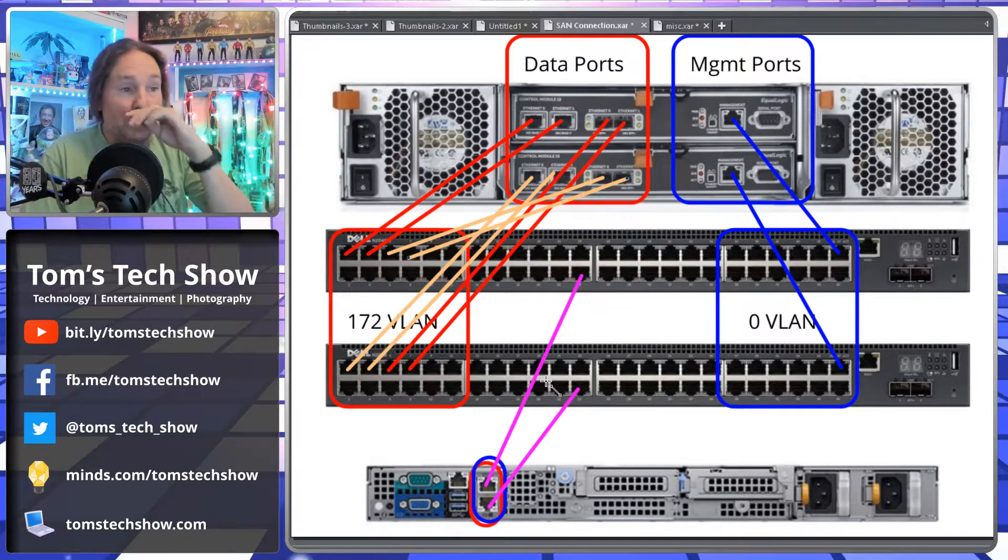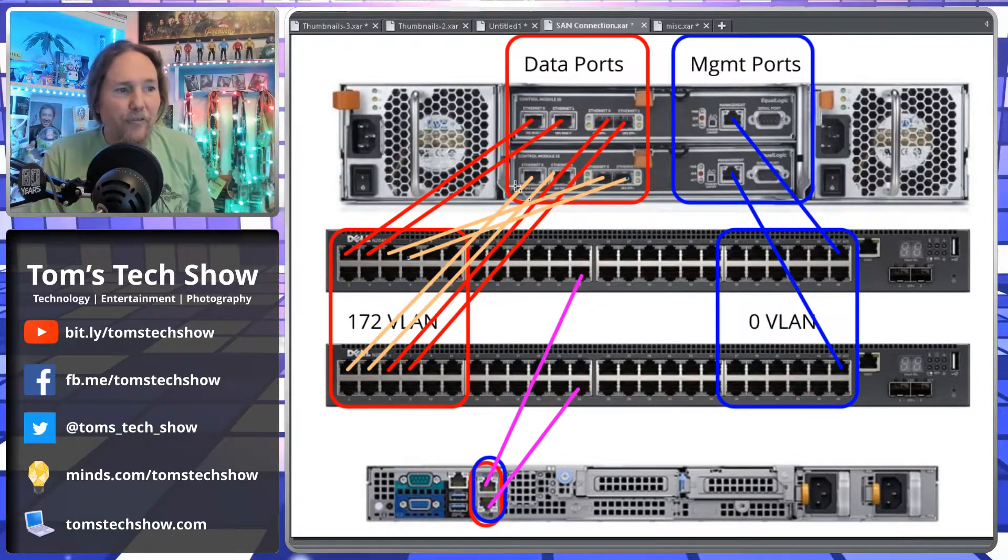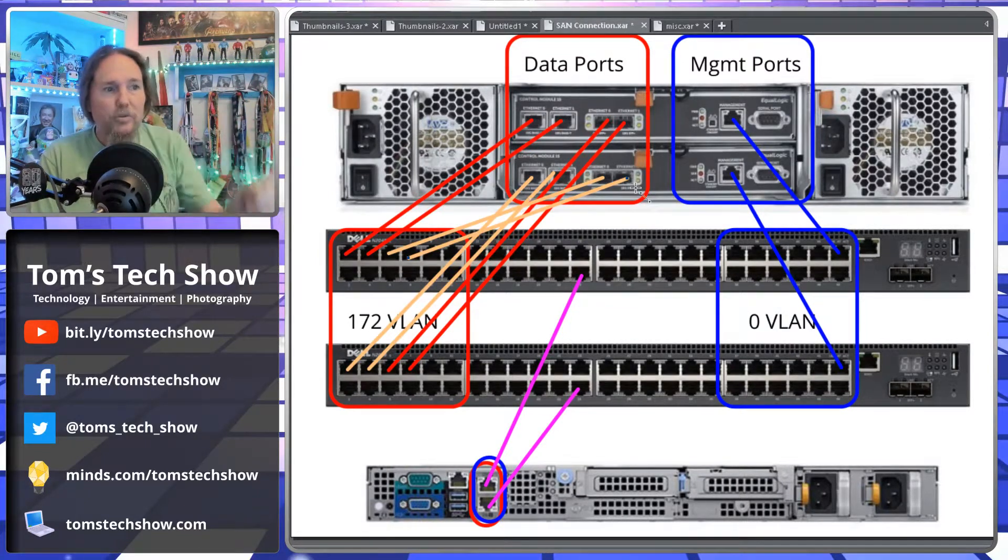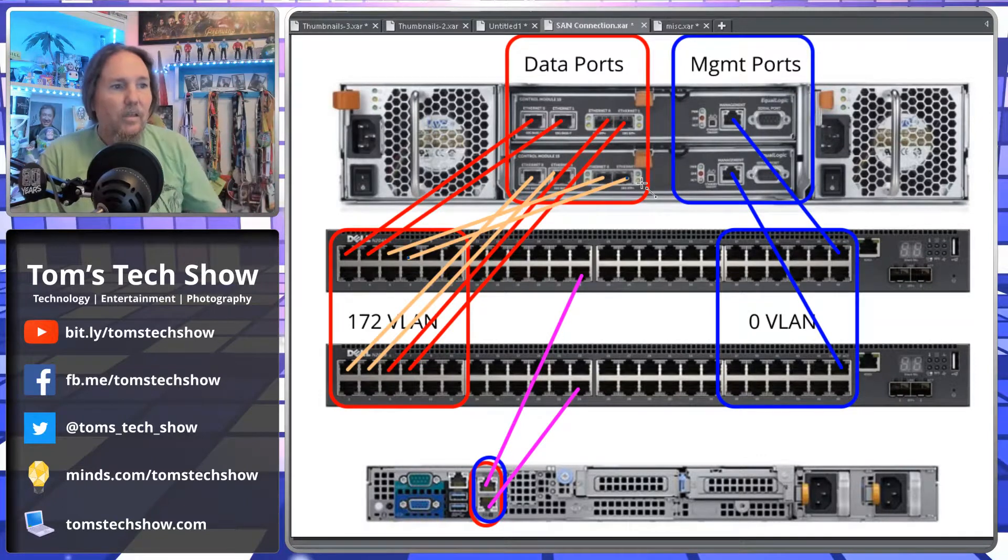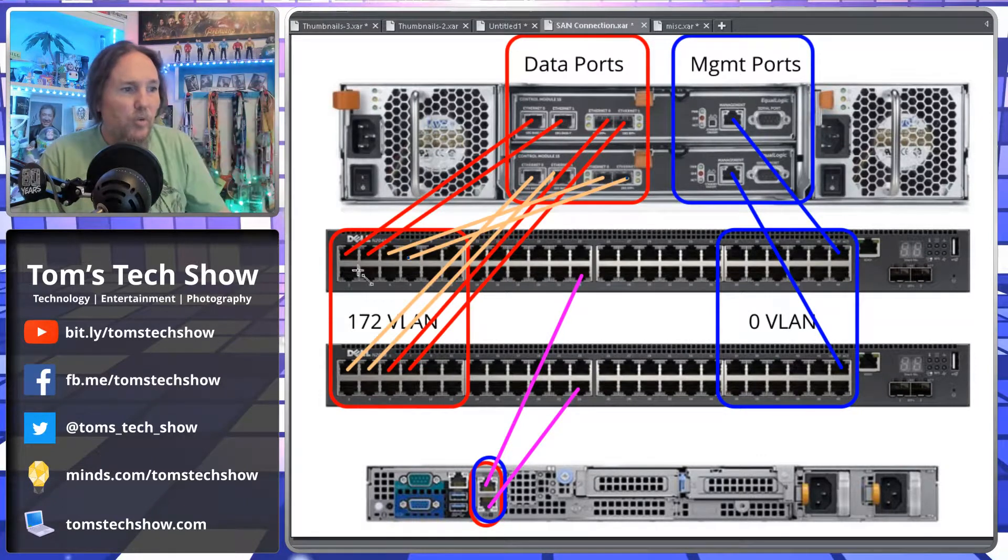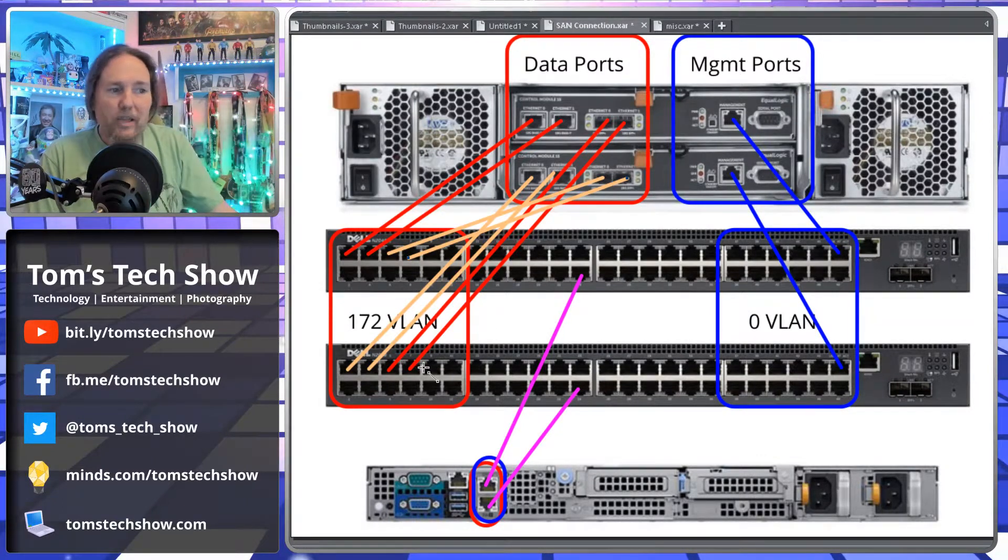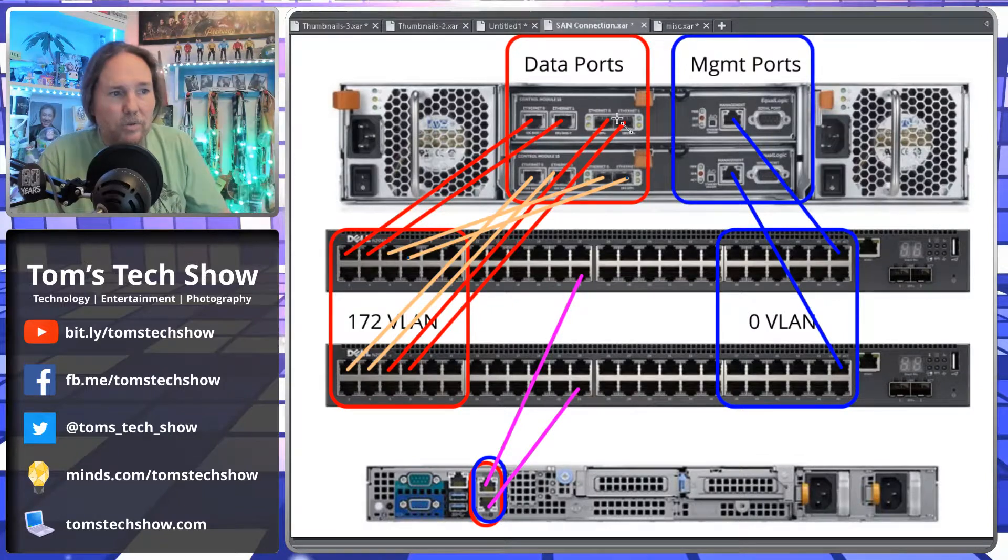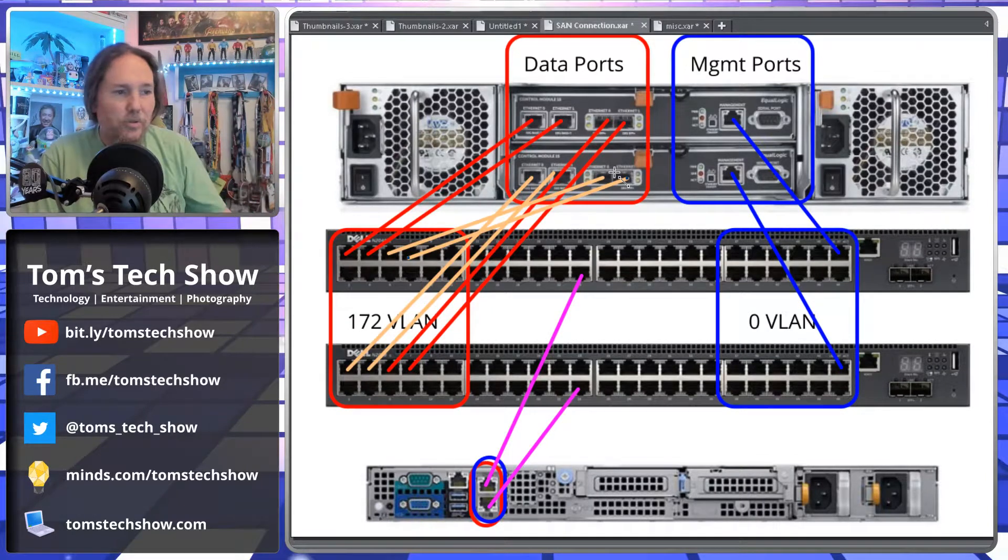So if we lose one of the controllers, then we still have four paths to the lower controller. If we lose one of these switches, we still have four paths, but two are to one controller and two are to the other controller.